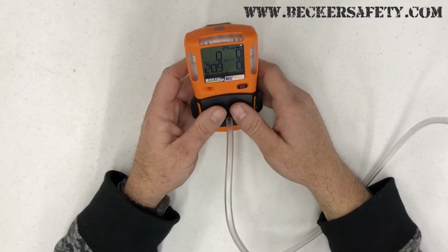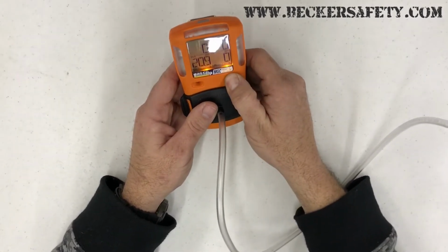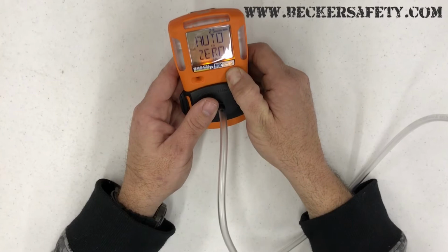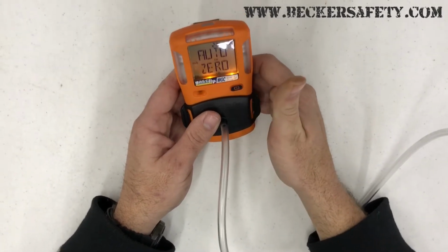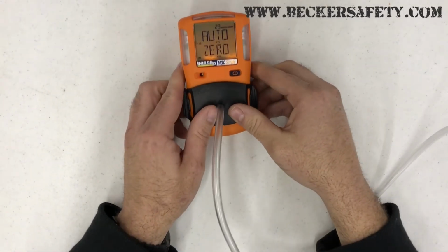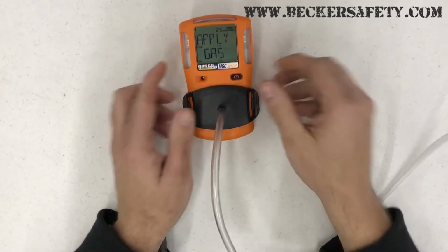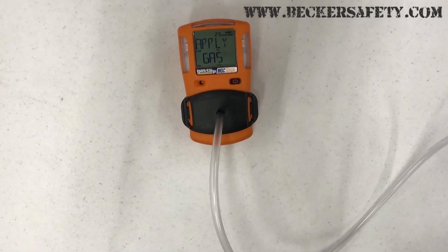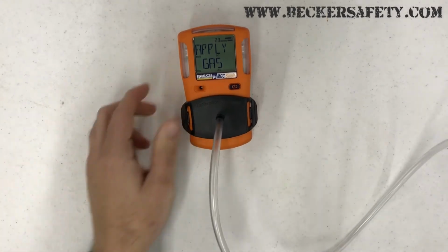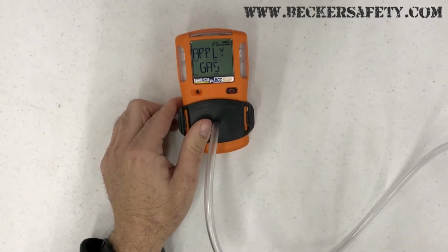You start off just the same as a fresh air cal. You press and hold the button. You keep holding the button until it says auto 0, and then you let the button go. When it says apply gas, you turn your gas on. And then you just wait for the sensors to span.